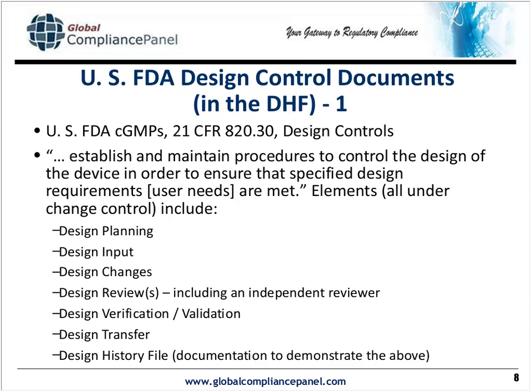Design verification is another of the elements, and design validation is a second element, and we'll define those two by virtue of a slide I'll show later. And then design transfer leading to the design history file. Now, depending on how you define that determines how you go about either closing out your history file or keeping it open for the entire life of your product.